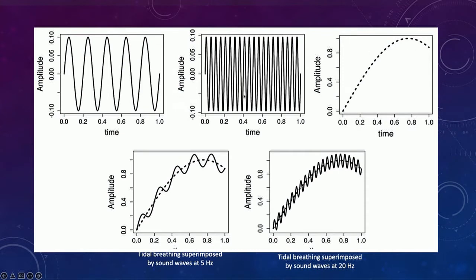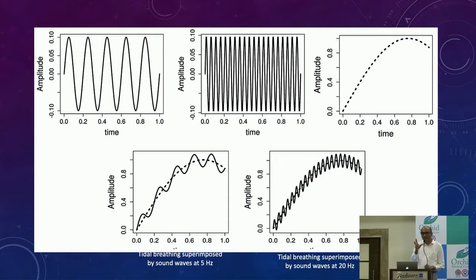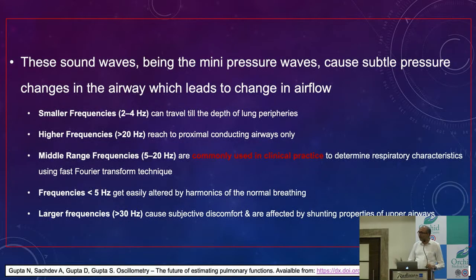Now when these sound waves are superimposed on the tidal breath, what we get is a composite pressure wave which goes inside, and this composite pressure wave comes back, and the machine can discriminate between the pressure changes of the tidal breath and the pressure and flow changes of the sound waves. That's how it can give us the results.